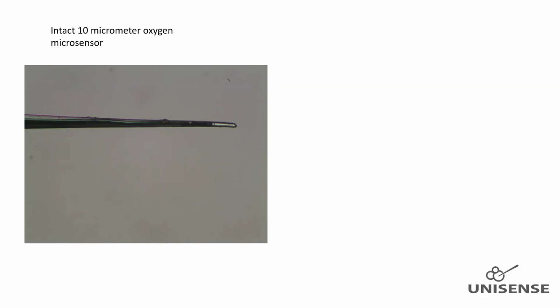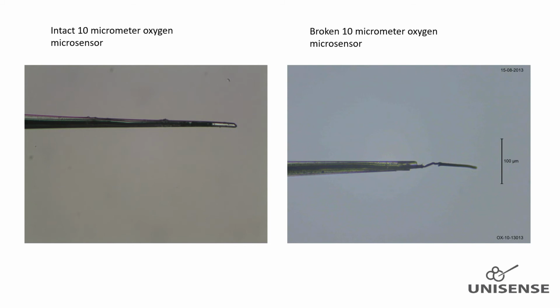I will now turn to troubleshooting oxygen microsensors which do not exhibit normal performance. Naturally, small glass tip sensors are fragile, and the tip might break if it hits something hard. This is a photo of an intact OX-10 sensor, and to the right a photo of the same sensor is shown, but now with a broken tip. It is seen how the working electrode is exposed as the glass tip is missing.